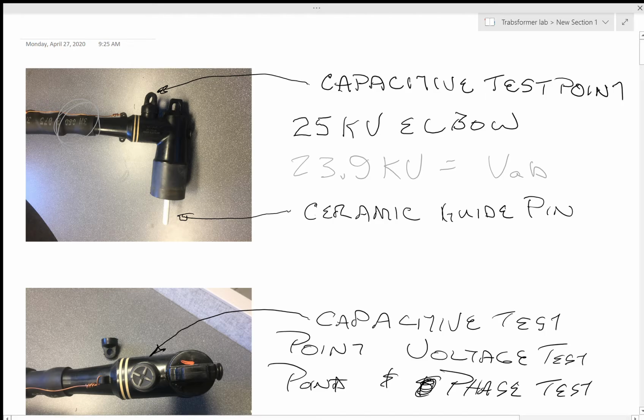This is a ceramic or capacitive test point right here. Basically, you can do a lot of things with that. You can check and see exactly what the voltage is, if you have the right meter. You can also go in there and compare, say, the A phases of two different lines and see if they are both the A phase. If you put your digital multimeter lead in that capacitive test point, and the voltage difference between the two is 0, then you're on the same phase. And if it's like 48, maybe 60 volts, then you're on the wrong phase.